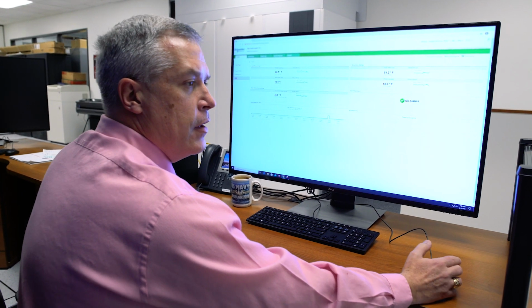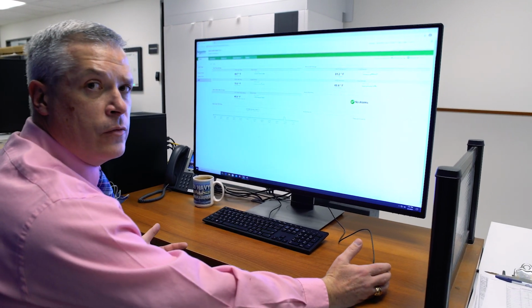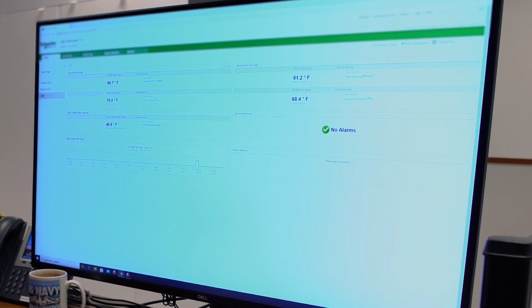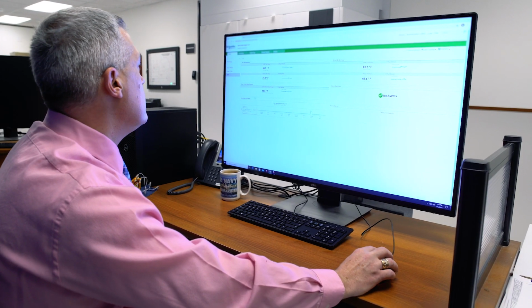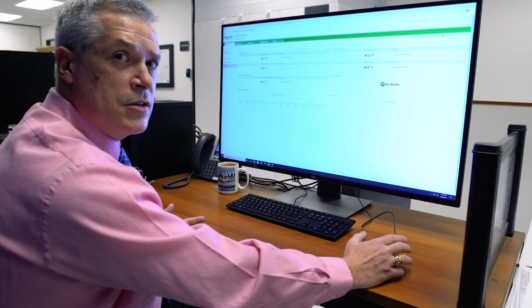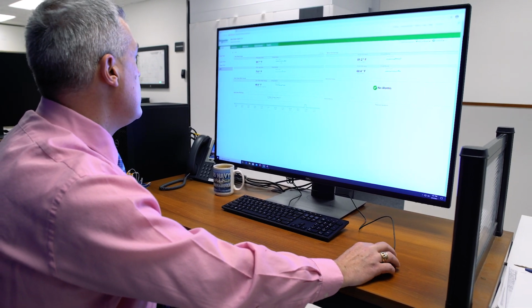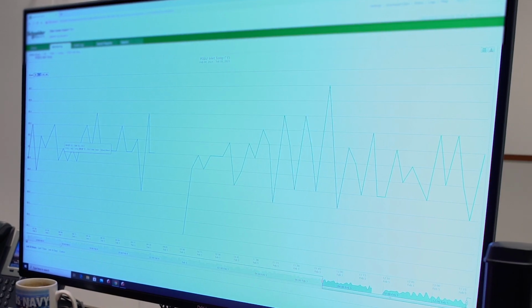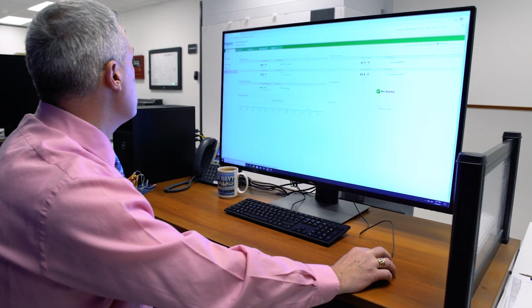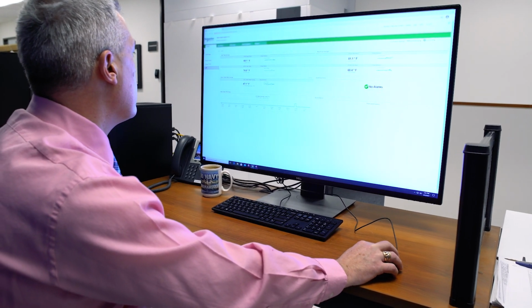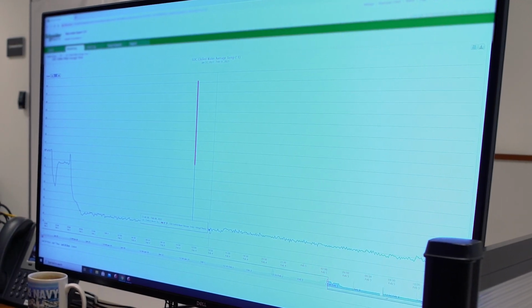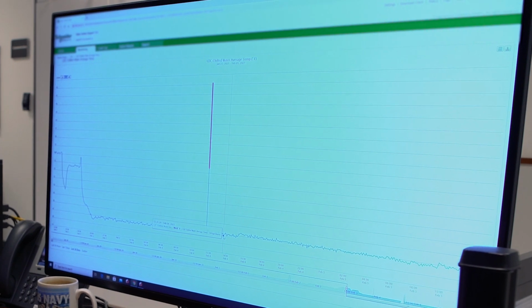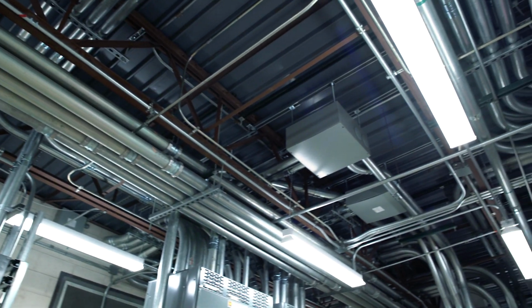Along with the data center installation, we received a data center information management software. It's a very powerful tool that allows us to see the operations inside the data center, including the average temperature of the racks and the air flowing in. We can also see important pieces like our chill water supply temperature, which gives a good indication of whether we're going to have a temperature outage before we actually see a rise in temperature.